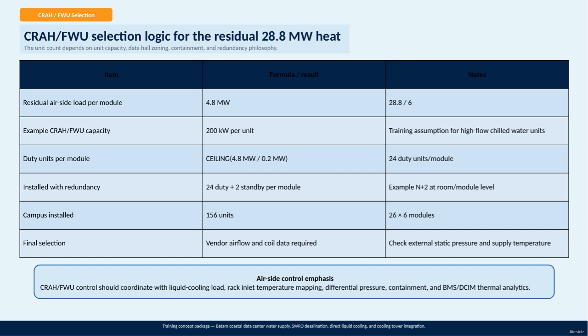The final selection process involves detailed vendor data, including airflow and coil performance. It's critical to verify external static pressure and supply temperature to ensure system compatibility and efficiency. Finally, control of the airside units is essential. CRAH and FWU controls need to work in harmony with the liquid cooling systems, monitoring rack inlet temperatures, differential pressures, containment effectiveness, and integrating feedback from building management systems and DCIM thermal analytics to maintain optimal environmental conditions.